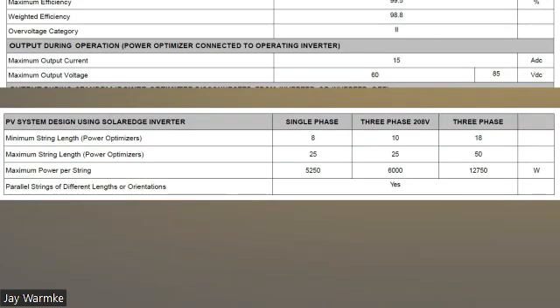So for the single phase optimizers, typically with SolarEdge for this size group, when you're hooking together a string, it's 8 minimum and 25 maximum. So I would recommend for SolarEdge, if you're installing an SolarEdge system and you're talking about a long distance between where the optimizers are and where the inverter is located, I would say any distance greater than 100 feet, 150 feet, I would consider increasing that minimum.